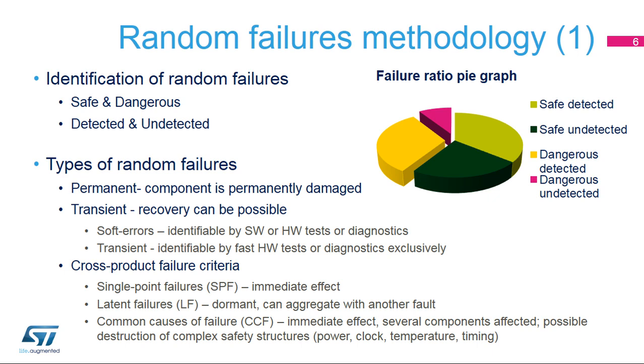For quantification purposes, safety standards recognize a safe failure fraction and diagnostic coverage. The safe failure fraction, or SFF, is the ratio of the rate of safe failures, including the rate of detected dangerous failures, to the total failure rate — safe failures as well as detected and undetected dangerous failures. The diagnostic coverage, or DC, is the ratio of the probability of detected dangerous failures to the probability of all dangerous failures.